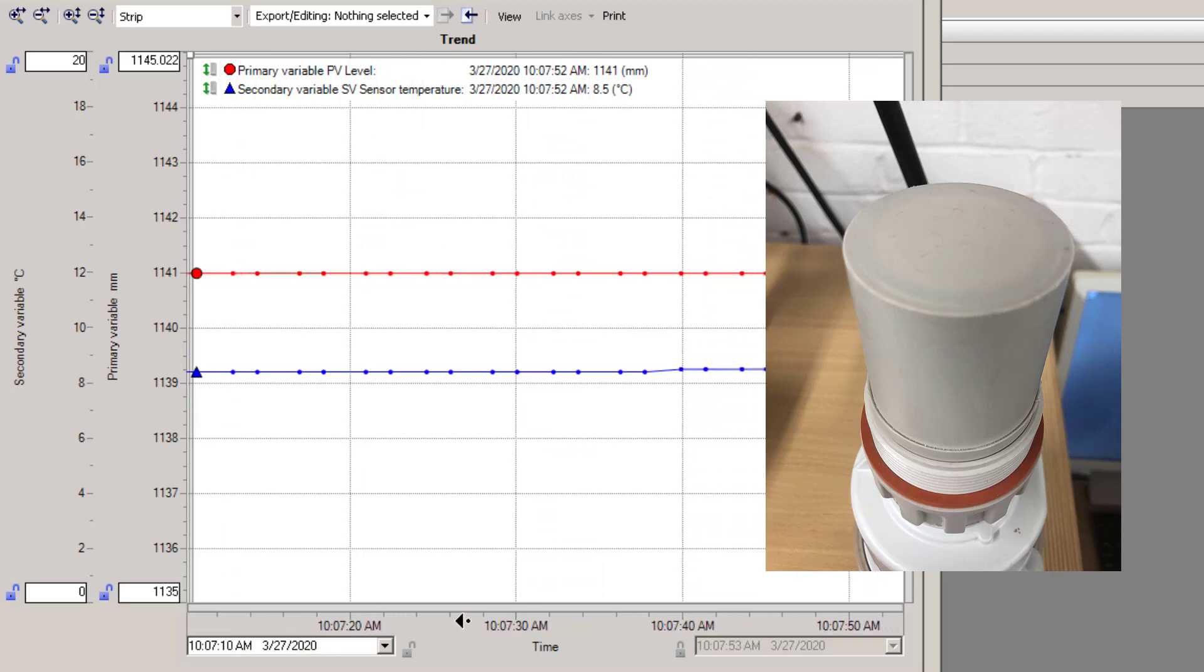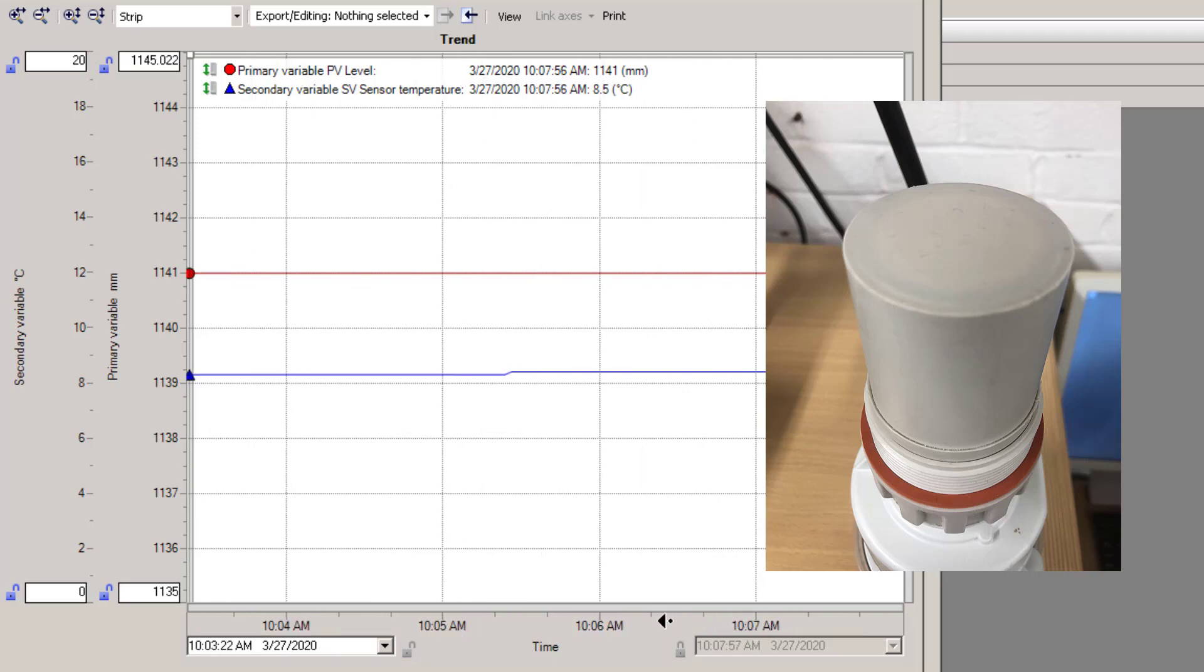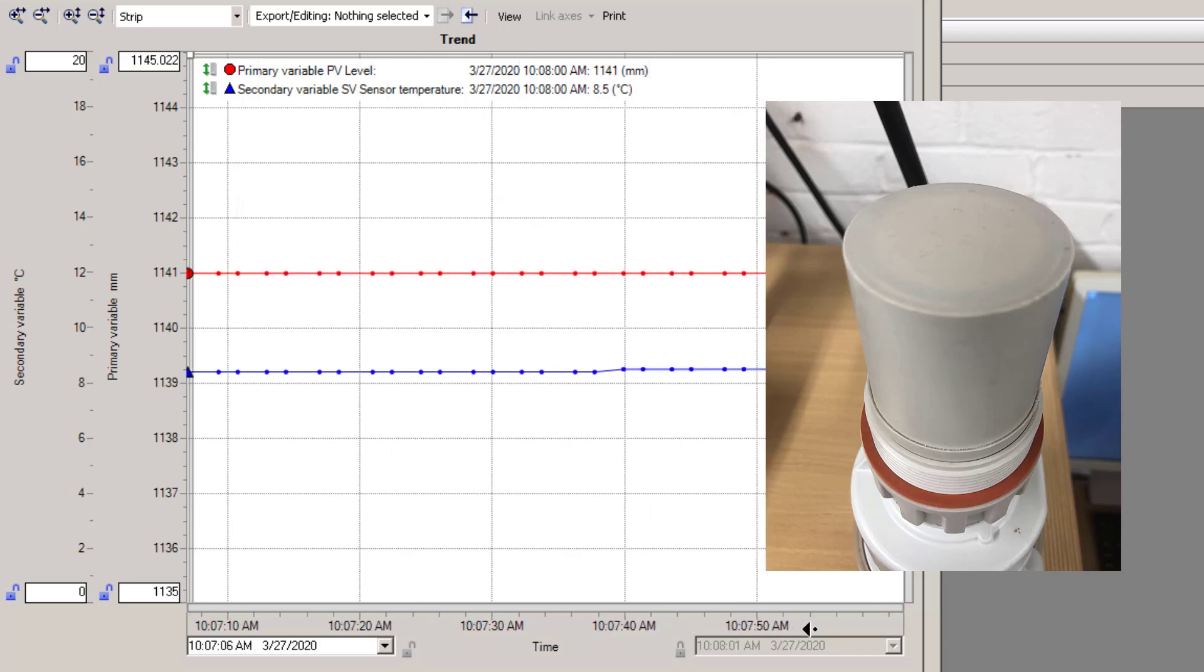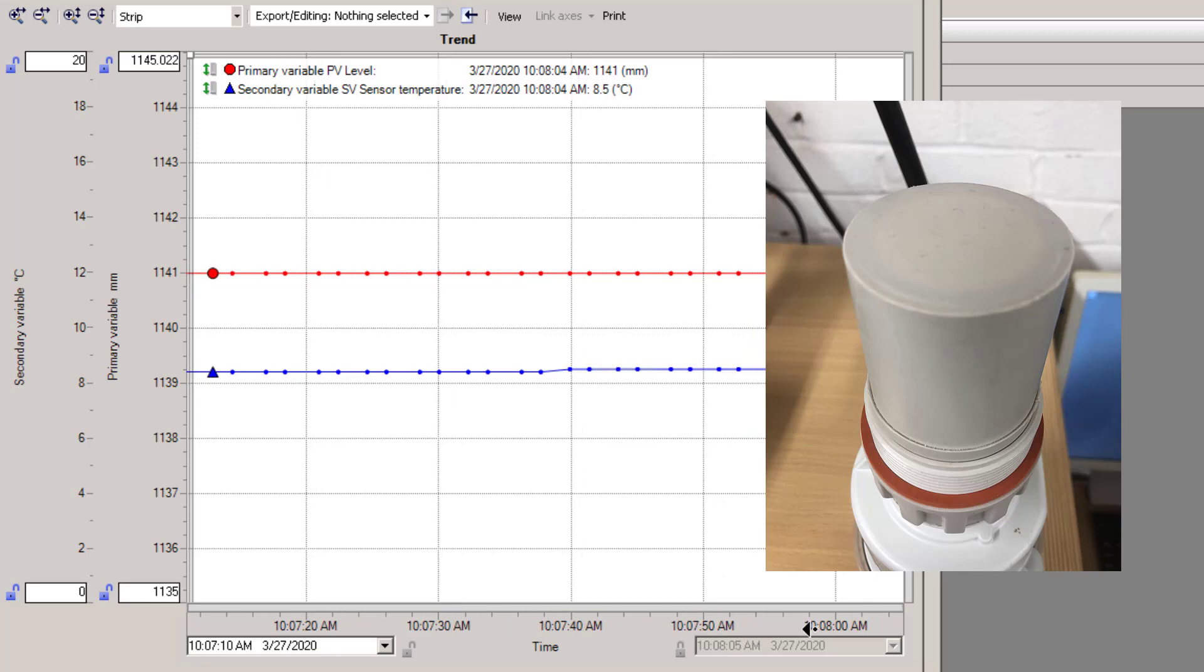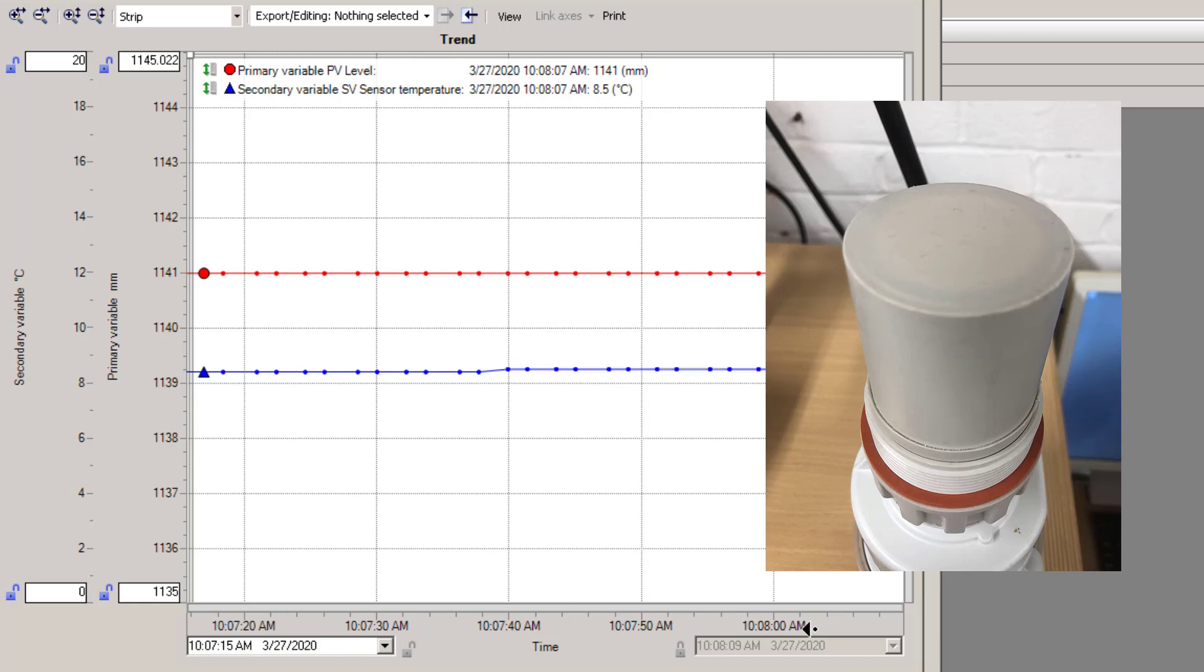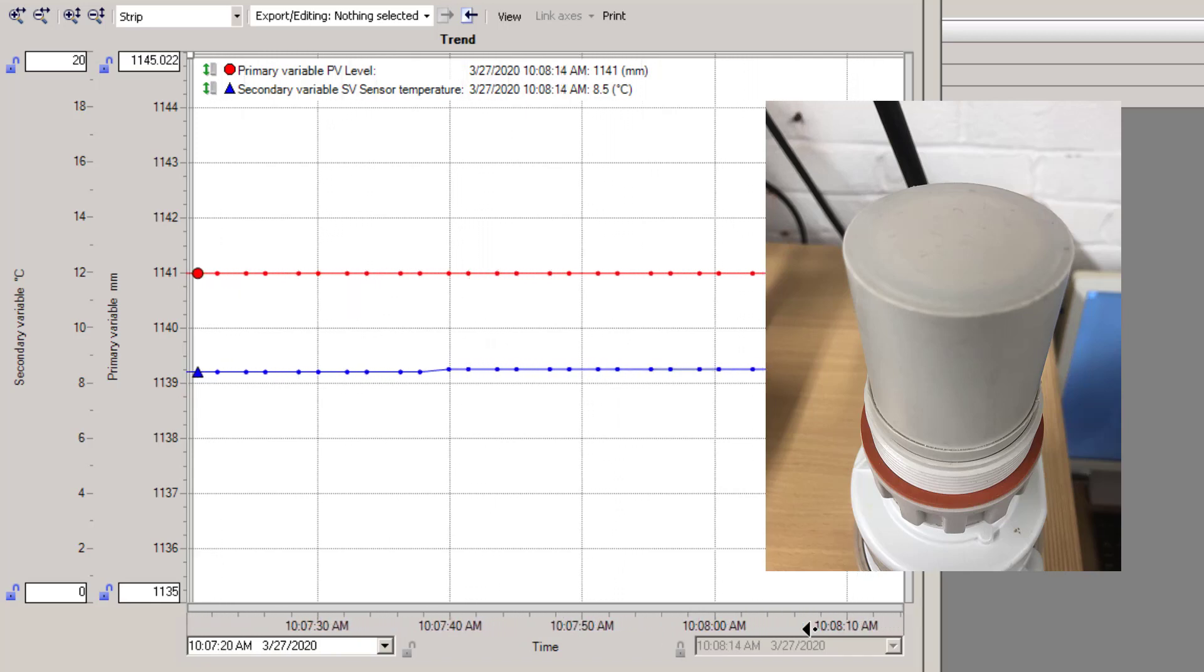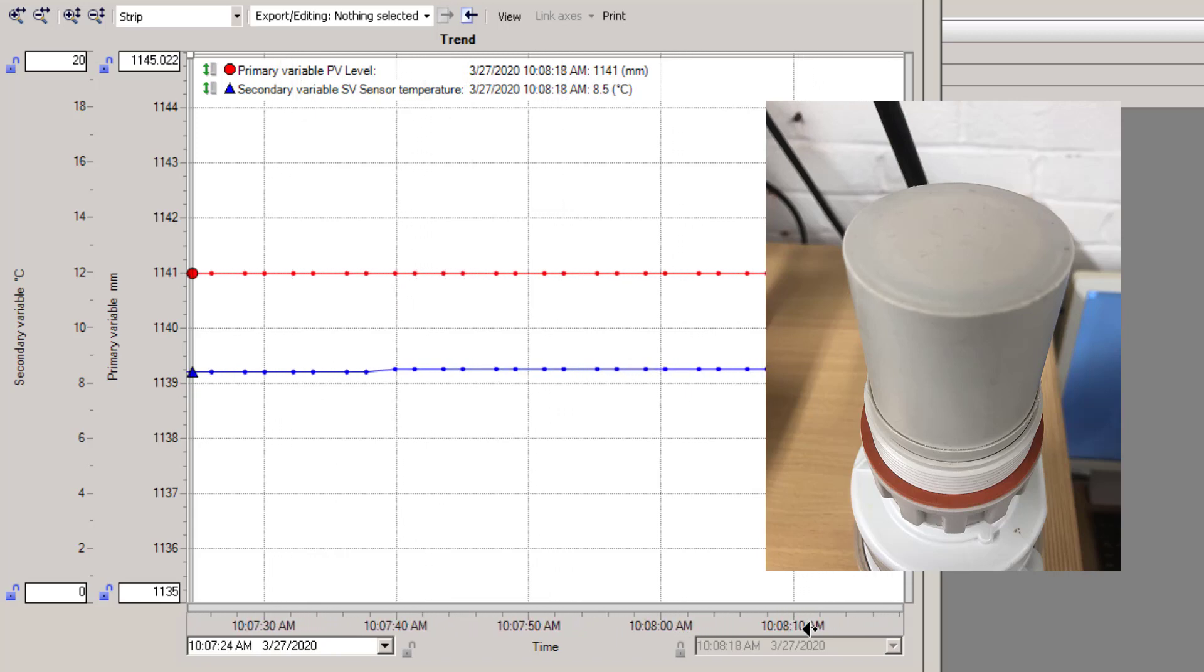We can see the bottom blue line is the temperature changing over time. This is more or less outside, it's in my garage. You can see there a small amount of water or condensation on the face of a Siemens ultrasonic transducer doesn't really affect the measurement because of the power of the crystal.